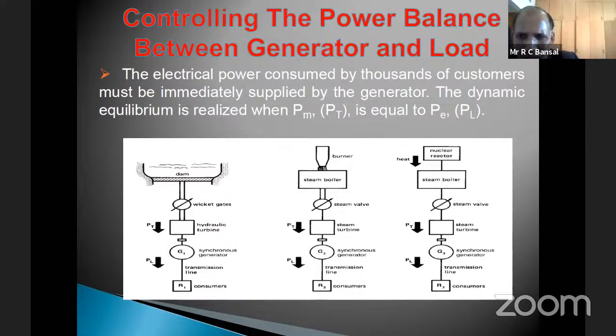Whereas the frequency deviation is minimal. The rated frequency is 50 hertz. It can deviate to 51 hertz, or go to 49. In an extreme case it can go to 52 hertz or 48 hertz, but frequency cannot go to something like 55 hertz. If that happens, everything will go into a blackout situation.